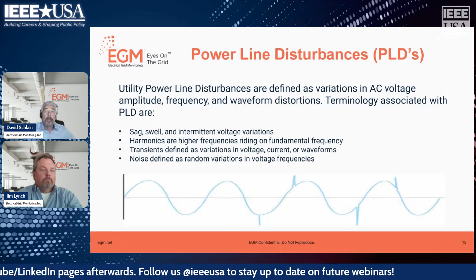One way we determine increased power line disturbances that can lead to areas of concern is what's called a PLD counter. We actually take these line disturbances and count them. If the frequency increases or increments, then we say, okay, there's something you need to look at, and we send a notification. The operator may notify the line crew to go out and check the area based on the locating capability.